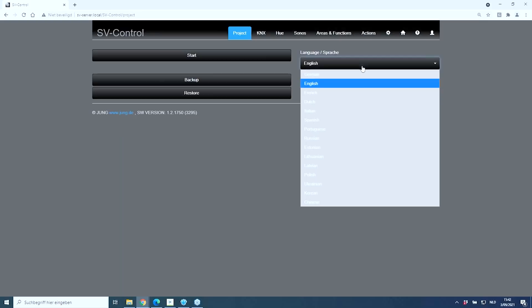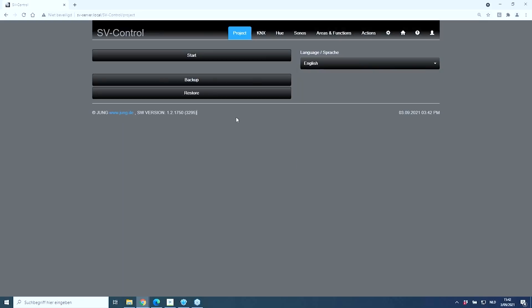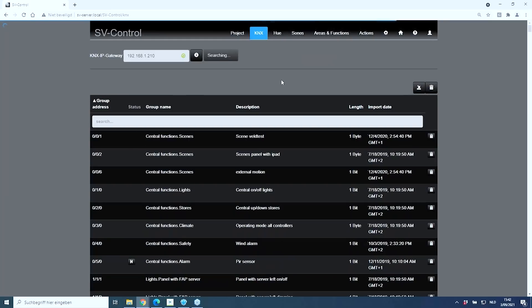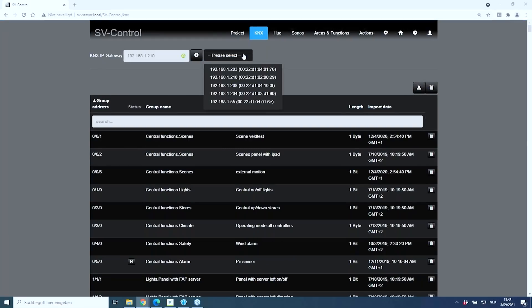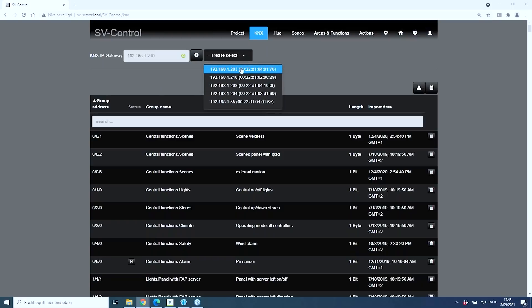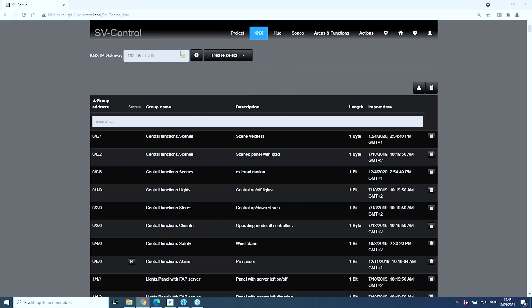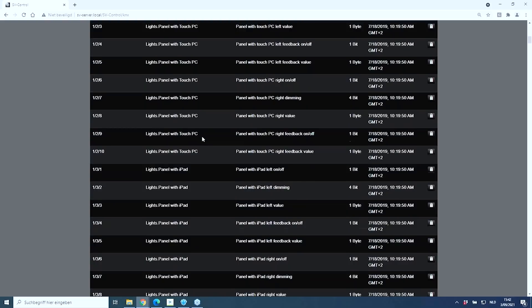First, we select the corresponding language and proceed with the KNX tab. The device scans for available IP interfaces — in many installations there will be just one to select. A green symbol indicates that the connection to the IP gateway is established. By pressing that symbol, we can import the project exported from ETS software in OPC format, making all group addresses available.